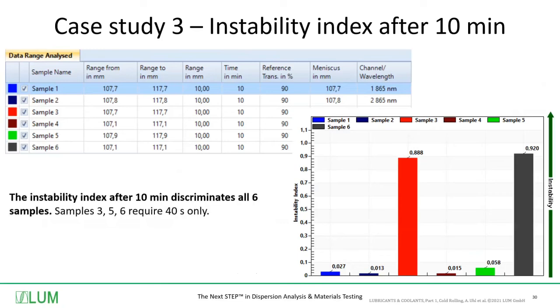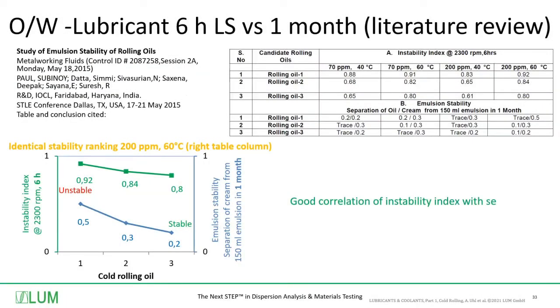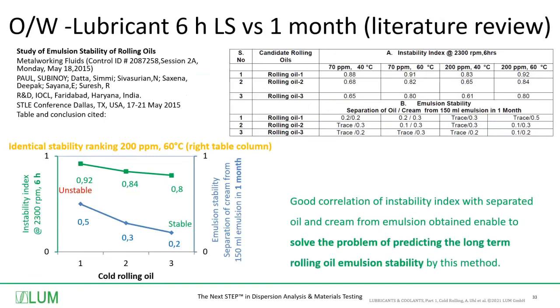After 10 minutes, we are able to discriminate all 6 samples. We can also see that only 40 seconds are needed for samples 3, 5, and 6 — same ranking: most unstable sample 6, second most unstable sample 3, third sample 5. Samples 1, 2, and 4 are close to each other, so we recommend running a few minutes longer — 40 seconds for the first three, 10 minutes for all six. The authors conclude there is a good correlation of the instability index with the separated oil and cream from emulsion, enabling prediction of long-term rolling oil emulsion stability. Six hours in the LumiSizer versus one month storage in a hot air oven.